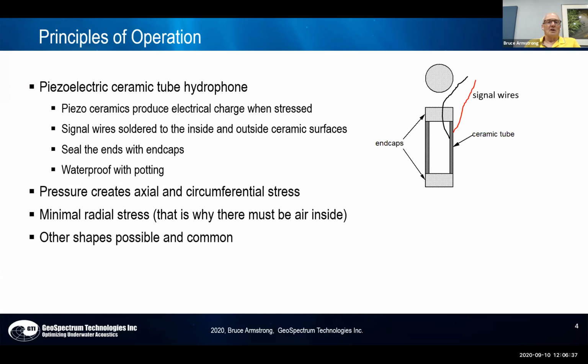So pressure hydrophones are, I show a simple one here. You take a piezoelectric ceramic tube, you put wires on the inside and the outside, you seal the ends with end caps, and then you put a bit of waterproofing around it. And that is your simplest hydrophone. So pressure creates axial and circumferential stress in the ceramic tube. That ceramic tube with the stress in it creates electrical charge. And in the construction of hydrophones, you always try to minimize some of the stresses in it. In this case, you have to minimize the radial stress, and that's why hydrophones have air inside them. If you did not have air inside the hydrophone, then you wouldn't have much of a hydrophone. Other shapes are possible and quite common. I've just showed you one of the simplest.